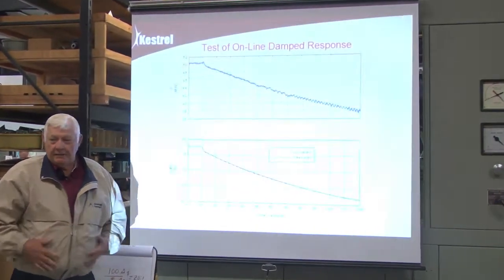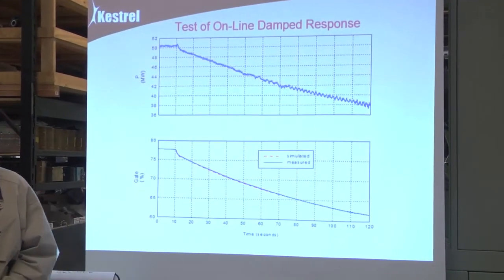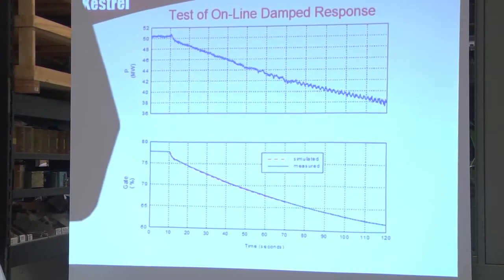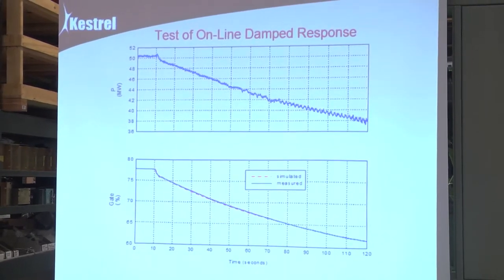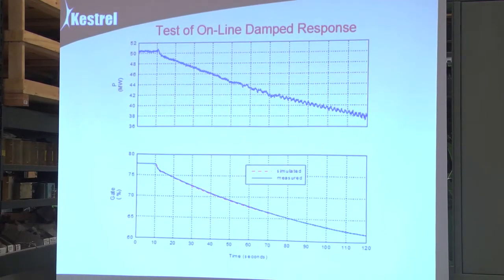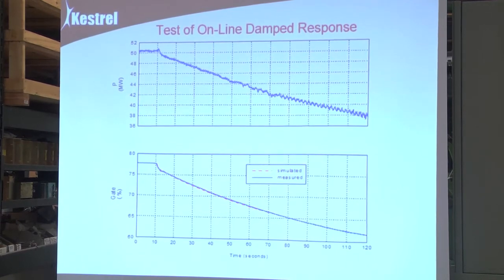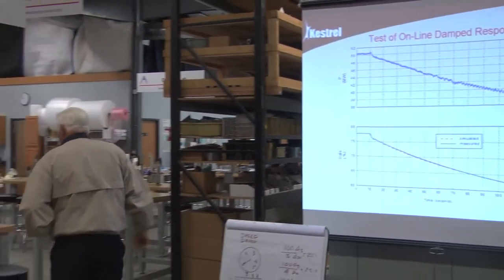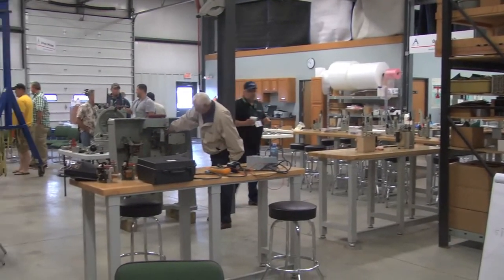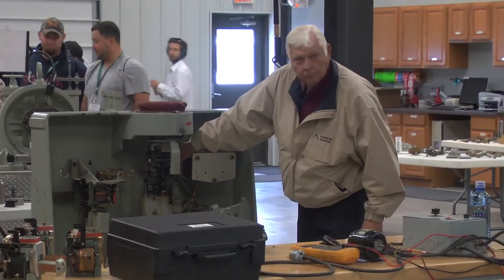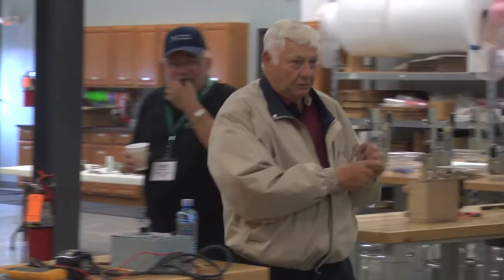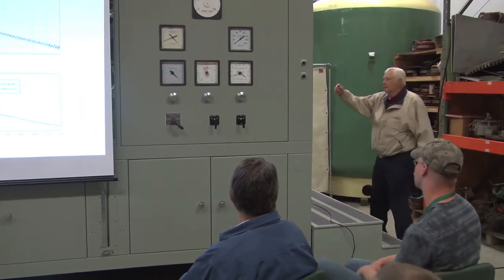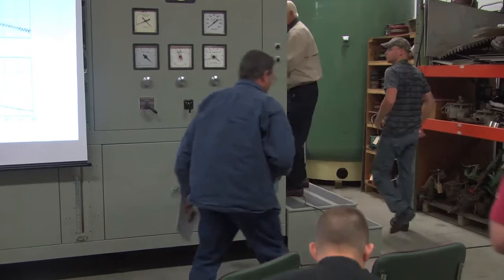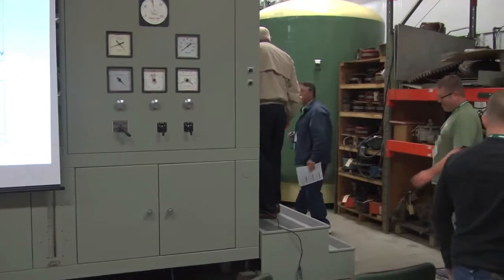The reciprocal of that, and I didn't bring my calculator. Take 1 divided by 2.5. 40%, right? Okay. On a Woodward unit, that would be maximum on the slider, which is right here on a Woodward unit. This is that calibrated dial, which you'll probably see when you do that test. On the Pelton unit, it's that slider here. This is your temporary droop adjustment, okay?